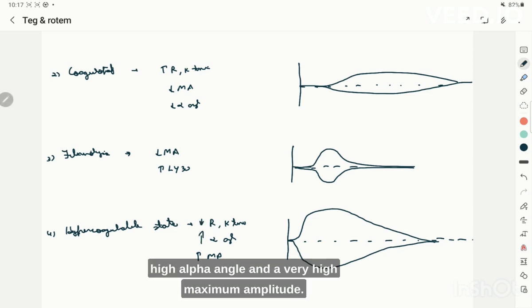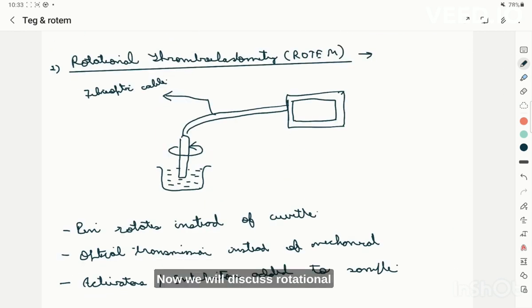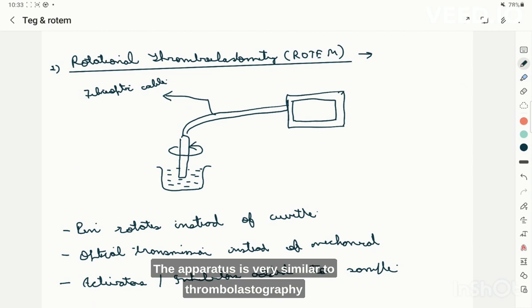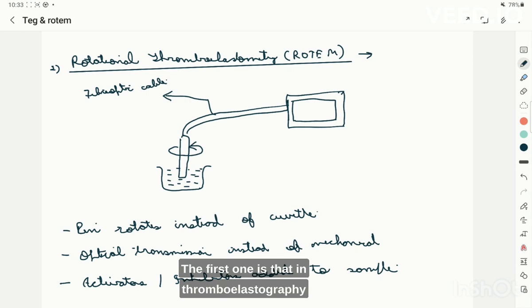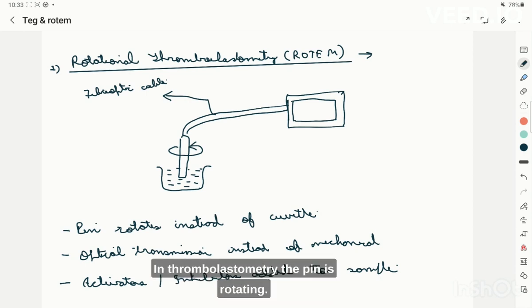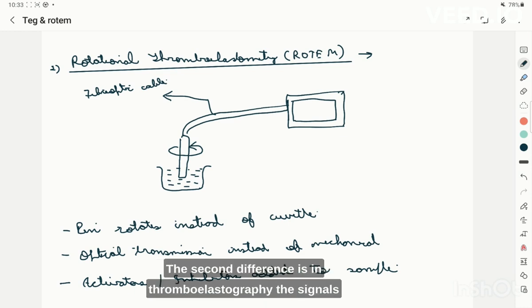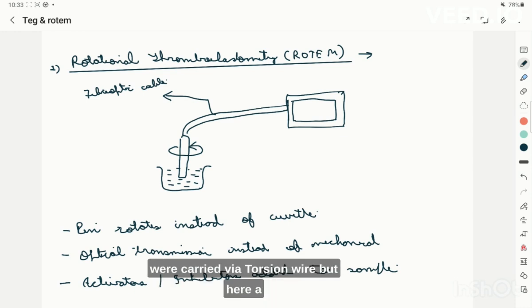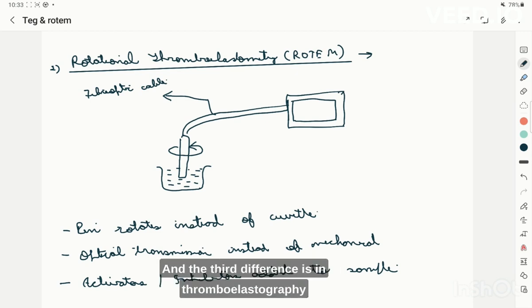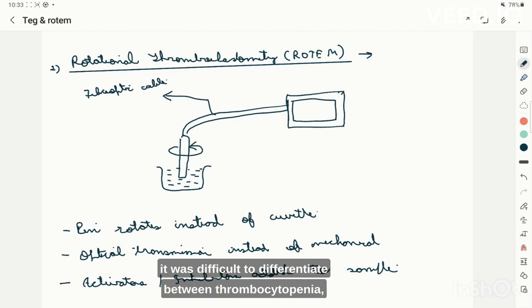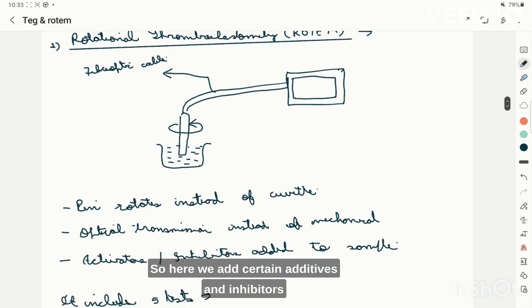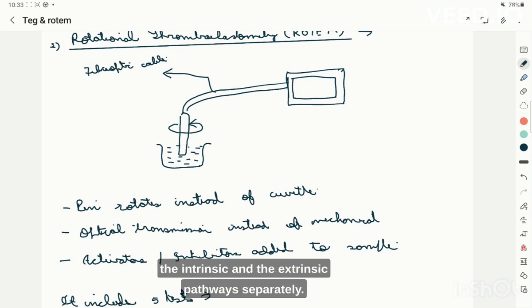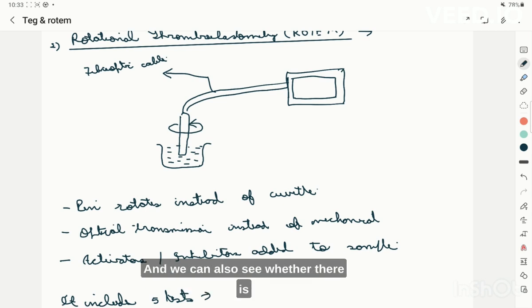We will now discuss rotational thromboelastometry — ROTEM. The apparatus is very similar to thromboelastography but with key differences. In TEG the cuvette rotates, whereas in ROTEM the pin rotates. In TEG signals are carried by a torsion wire, but in ROTEM a fiber optic cable is used. Additionally, ROTEM adds certain activators and inhibitors and uses different activations to test the intrinsic and extrinsic pathways separately.